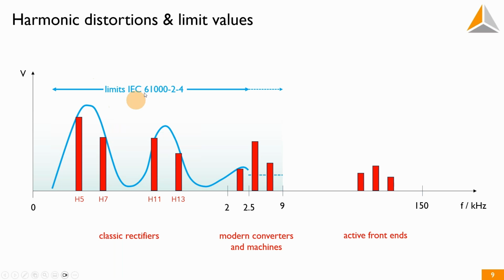So here I display the limits of the IEC 61000-2-4 for industrial power grids, which has limit values for the harmonics up to the 50th order, so 2.5 kilohertz, and recommendations for up to 9 kilohertz. But everything above 9 kilohertz is totally neglected. So our 28 kilohertz problem with a crane wouldn't even be considered in here.